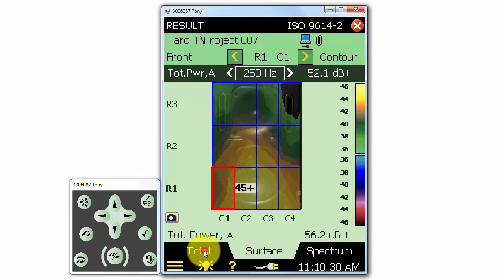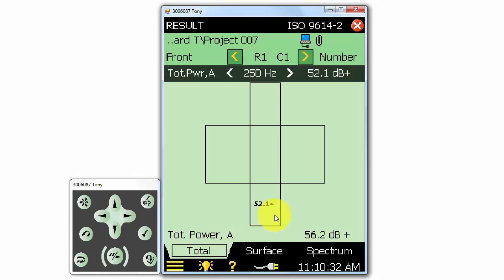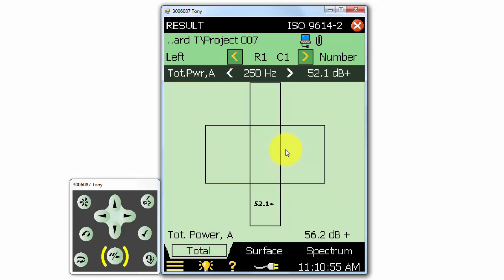The Total tab will allow us to view the total results for the entire object. Here we see the overall sound power result of the 250 Hz band for the front of the measurement surface. The total A-weighted power is also displayed at the bottom of the screen. We can exit the Results section and return to making measurements by clicking on the red X at the top right.